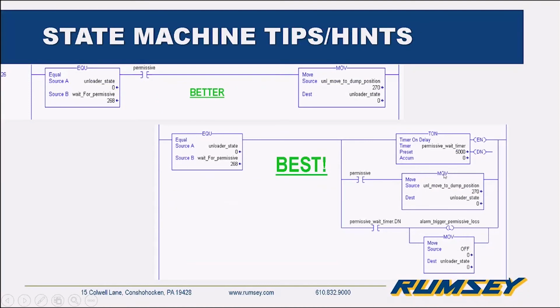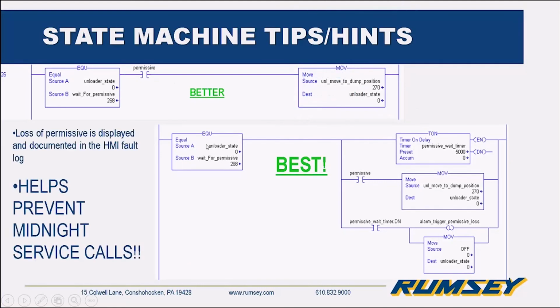Taking it yet another step further would be to throw a watchdog or a wait timer of sorts into your code. So we're out here, waiting for the thing that we have to happen. Built into the code, at each rung we have a watchdog timer that starts timing as soon as we get into the state. If the permissive is made, we move on. If not, create a fault, move it to the off position and announce it on the HMI so they can troubleshoot just the thing associated with what it was telling it to do. Maybe the loader was not full, or the prox switch cable had been stepped on and broken, or whatever that is. This might be the best way to manage your state machine for troubleshooting purposes and prevent people from calling you.